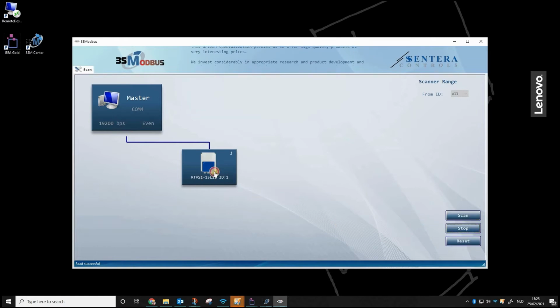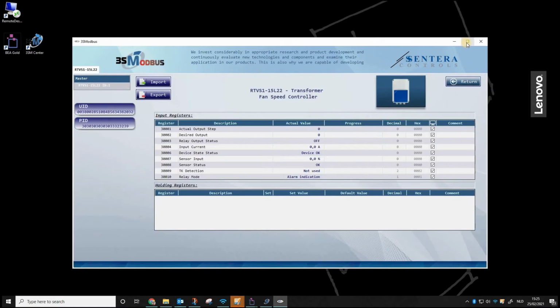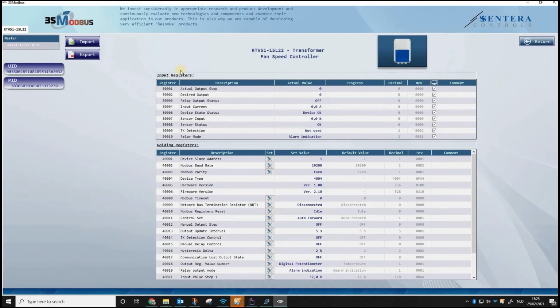If we click on the icon, we enter the screen of the Modbus registers, and on the one hand we see input registers, where we can read everything that is sent to the output as well as the status fields. And on the other hand, we see the holding registers in which we can change parameters by clicking on these icons. We see here that the current output step of the RTVS is 0, and this is correct because the desired step is also set to 0.